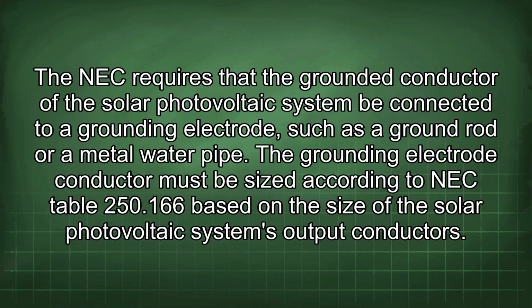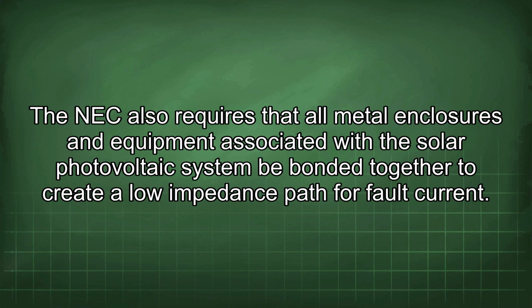The grounding electrode conductor must be sized according to NEC table 250.166 based on the size of the solar photovoltaic system's output conductors. The NEC also requires that all metal enclosures and equipment associated with the solar photovoltaic system be bonded together to create a low impedance path for fault current.